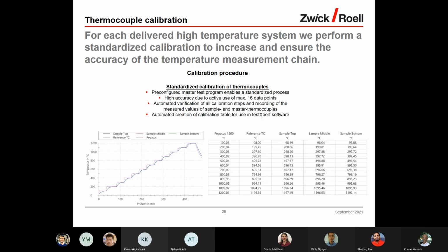For each delivered high temperature system, we perform a standardized calibration to increase and ensure the accuracy of the temperature measurement chain. The calibration procedure: standardized calibration of thermocouples with pre-configured master tests enables a standardized process and high accuracy, with use of a maximum of 16 data points. At this moment, we only have 12 data points. Automated verification of all calibration steps and recording of the measurement values of sample and master thermocouples. Automated creation of a calibration table for use in the testXpert software.